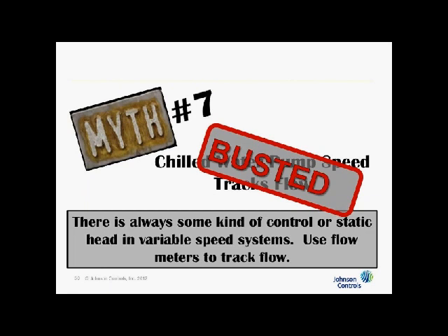And there's a derivative to that myth: if speed doesn't track flow and flow doesn't track load, then speed doesn't track load. You really need to use flow times delta T to calculate load. That means you really can't avoid flow meters if you want to optimize your plant. And remember, the whole seminar is about how to design the plant for the best efficiency. You need flow meters, and you need good flow meters that can measure well and stay in calibration.